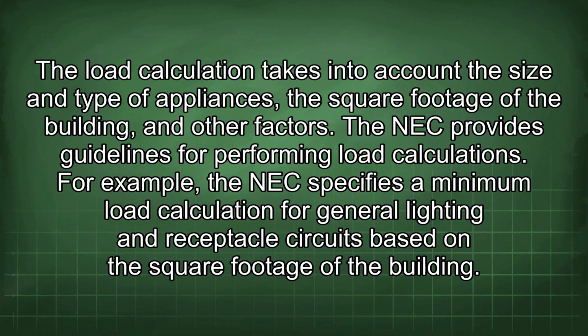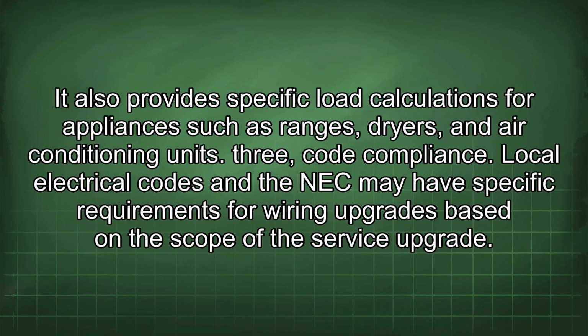For example, the NEC specifies a minimum load calculation for general lighting and receptacle circuits based on the square footage of the building. It also provides specific load calculations for appliances such as ranges, dryers, and air conditioning units.